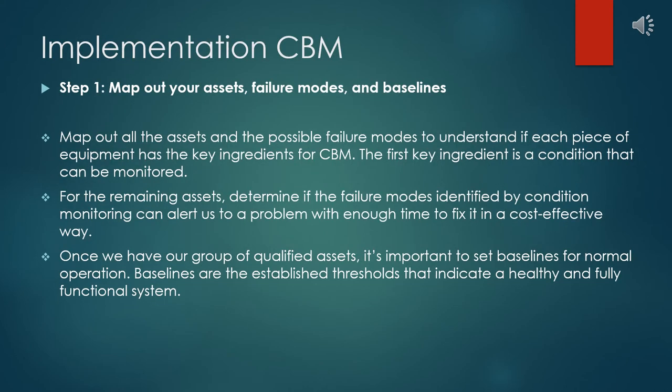Here are the CBM implementation steps. Step 1: map out your asset failure modes and baselines. Map out all the assets and possible failure modes to understand if each piece of equipment has the key ingredients for CBM. The first key ingredient is a condition that can be monitored. Condition monitoring doesn't work for every asset, so knowing which ones don't support sensors or other monitoring tools can save time and money. For the remaining assets, determine if the failure modes identified by condition monitoring allow enough time to fix a problem in a cost-effective way.